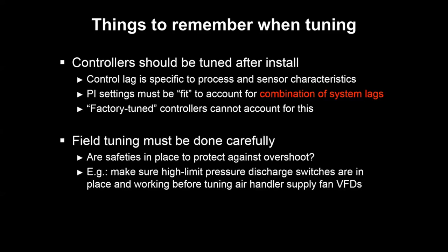And also this has to be done safely. One of the things to keep in mind with things like pressure and temperature, as you're introducing some new loop or trying to tune things, is that you want to make sure there are safeties in place that will protect the equipment if you have overshoot as you're tuning or when you're done with the loop. An example would be putting in something like a duct static pressure reset sequence. That may be adjusting your set point and throwing your fan speed around in a way that you may see a very instantaneous high gain in your duct.